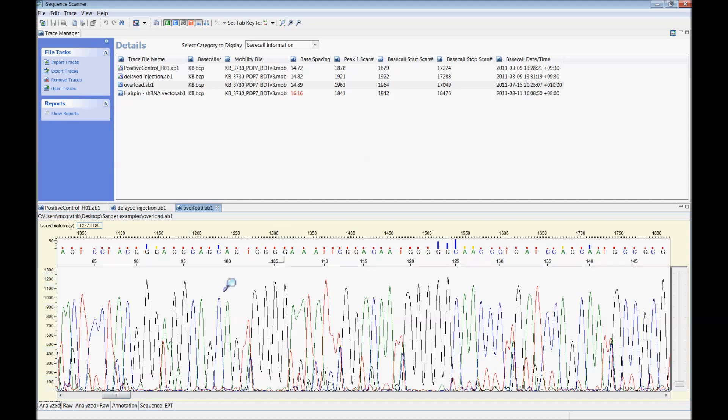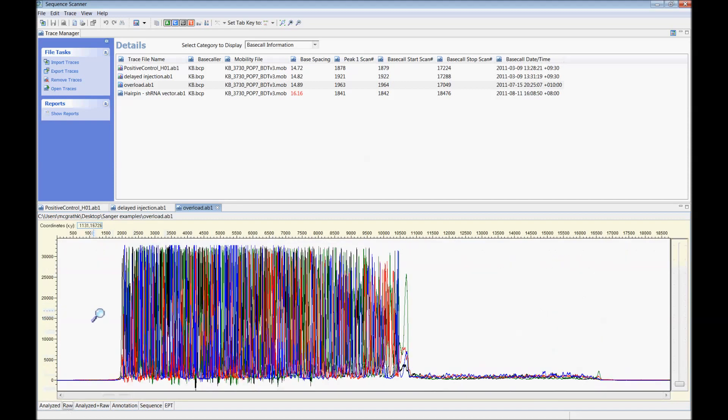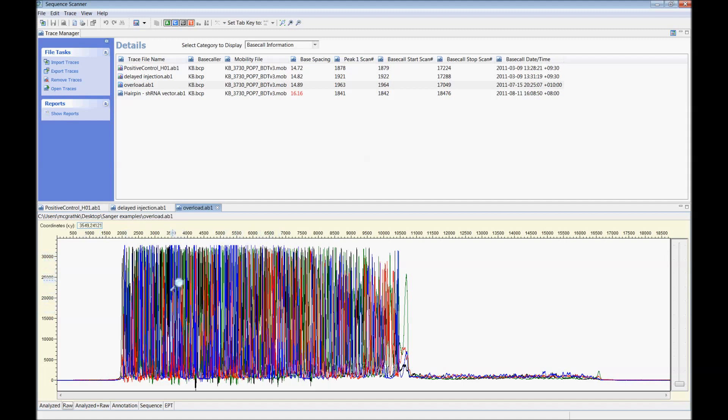The raw view of this shows a flat top effect with all the peaks maxing out on the detector and the relative fluorescent units being above 30,000. Using less template in this submission or reaction will result in a much cleaner read and bring those peak levels down into the detectable window between 1,000 and 30,000 RFU.